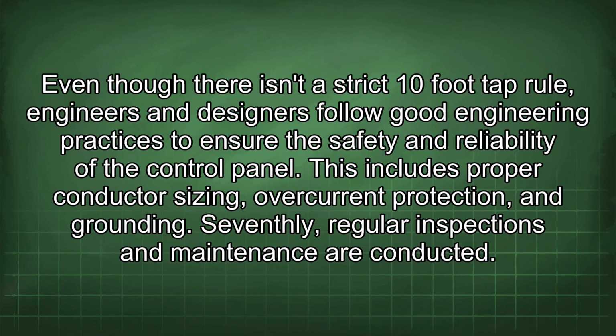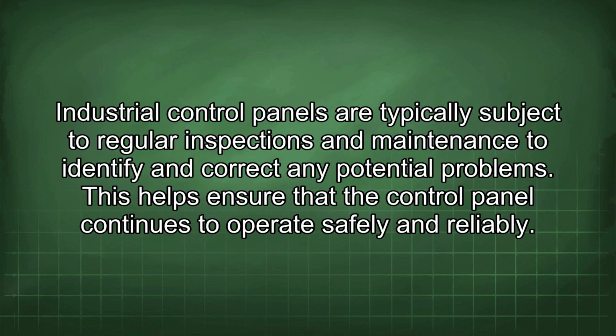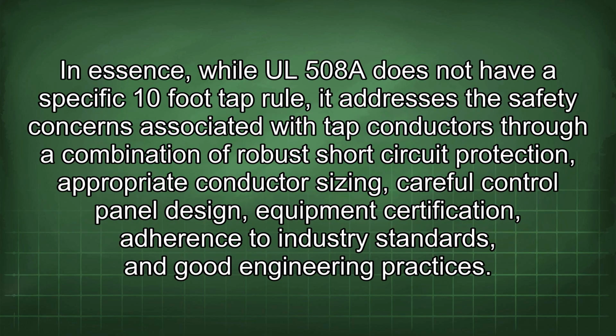Seventhly, regular inspections and maintenance are conducted. Industrial control panels are typically subject to regular inspections and maintenance to identify and correct any potential problems. This helps ensure that the control panel continues to operate safely and reliably. In essence, while UL 508A does not have a specific 10-foot tap rule, it addresses the safety concerns associated with tap conductors through a combination of robust short-circuit protection, appropriate conductor sizing, careful control panel design, equipment certification, adherence to industry standards, and good engineering practices.